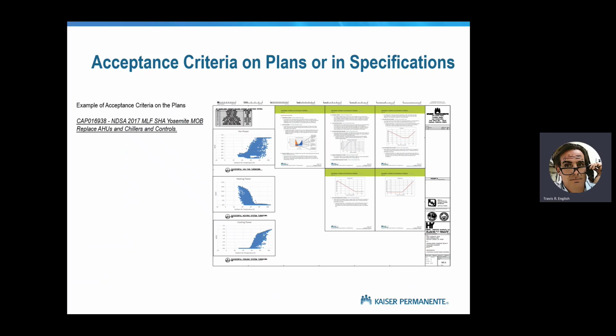I think I already said, if you want to check the fan power, you have to put a fan power point in your controls. If you want to check the cooling power, you have to put the cooling power point in your controls, right? The other thing that I'll point out here, you'll notice that on this sheet of plans, there are 2 professional engineer stamps.